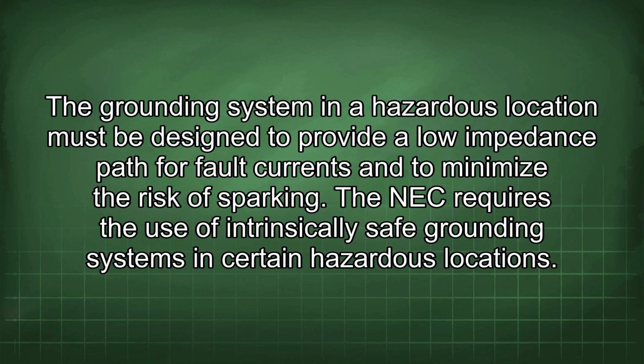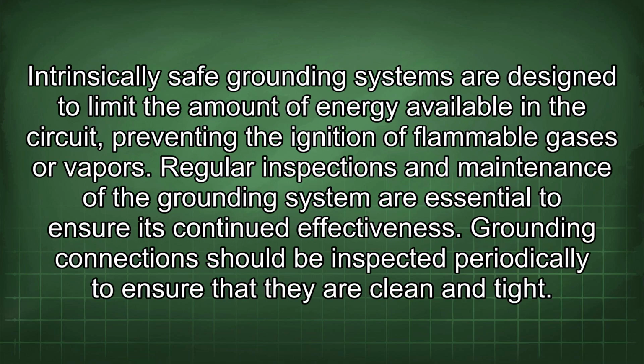The NEC requires the use of intrinsically safe grounding systems in certain hazardous locations. Intrinsically safe grounding systems are designed to limit the amount of energy available in the circuit, preventing the ignition of flammable gases or vapors. Regular inspections and maintenance of the grounding system are essential to ensure its continued effectiveness.